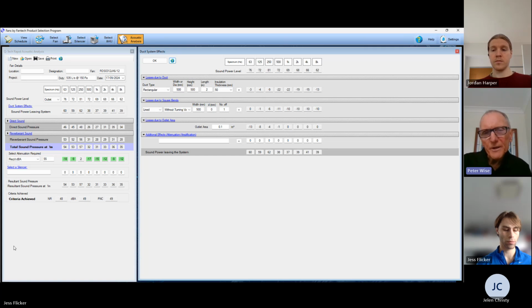And because it's a factory and a sort of noisy place, we didn't put any attenuation in to start with - we didn't think we needed it. And when we started the fans up and got it all running, we had a noise level in the space of about 70 dBA. So it was too noisy. It was kind of, you could say maybe borderline, but for someone to be working in that space all day at 70 dBA, it was too noisy.